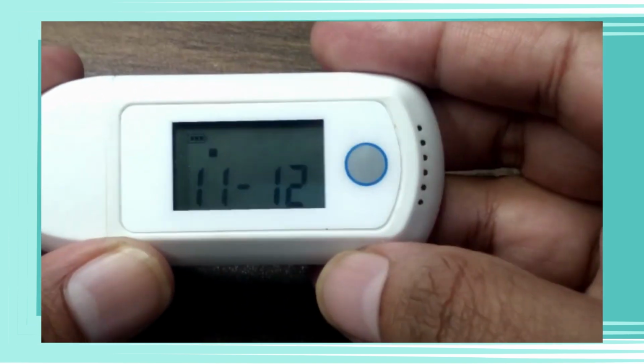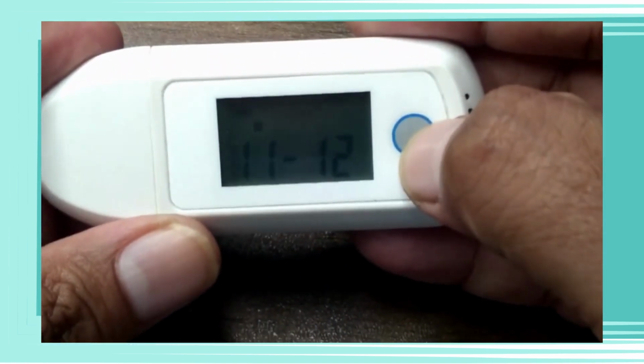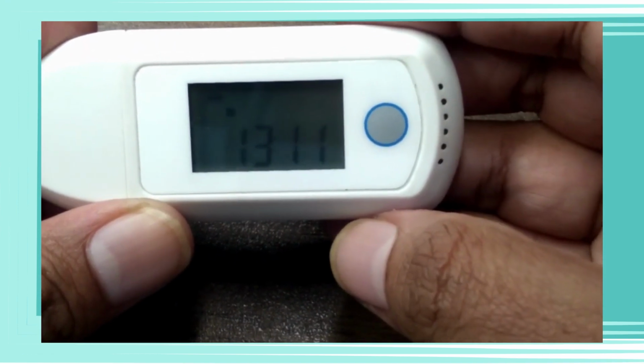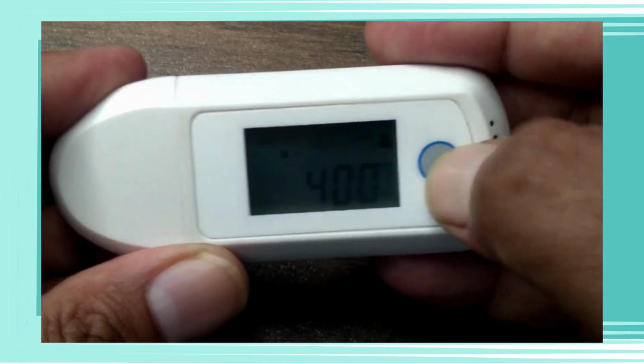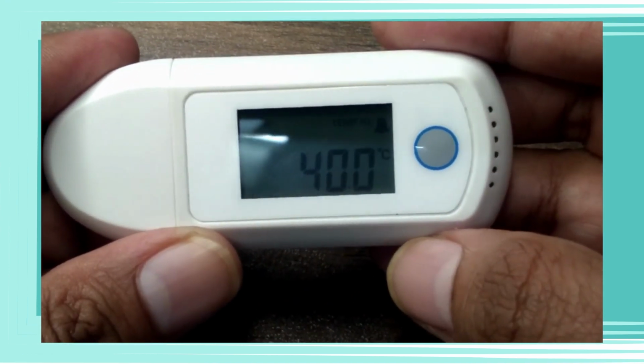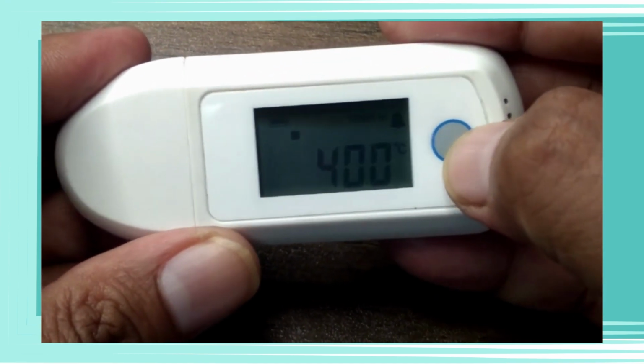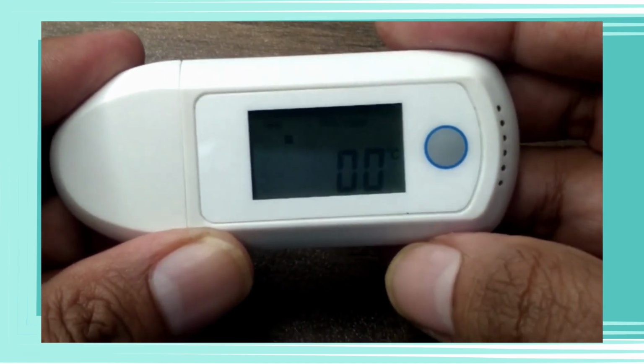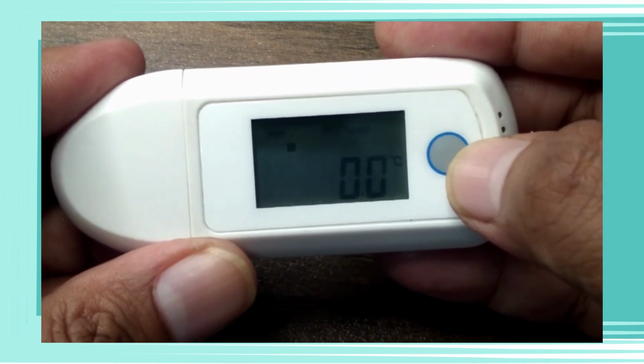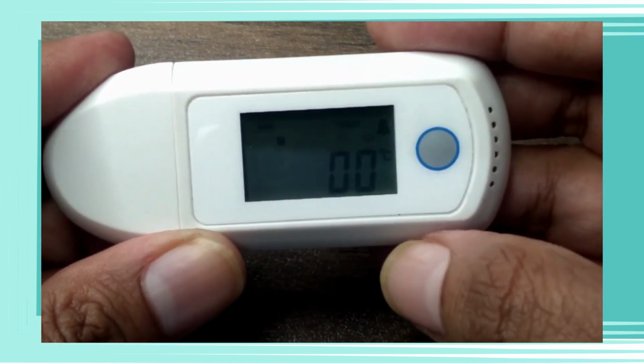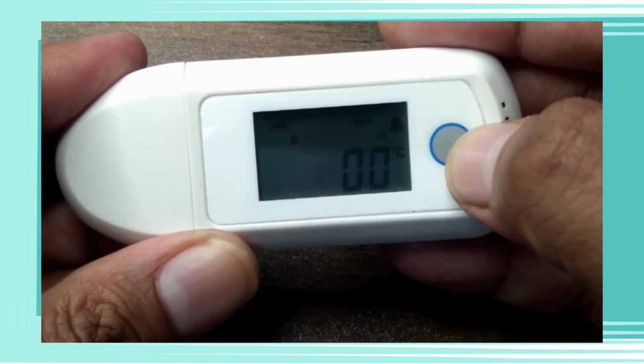Now again if we push the button we can see the date as well. Now let's again push the button, we can see the time as well. After again going into same, we can set the high alarm. After again clicking the button, we can see the low alarm. By doing this same process again, we can do settings for humidity also.